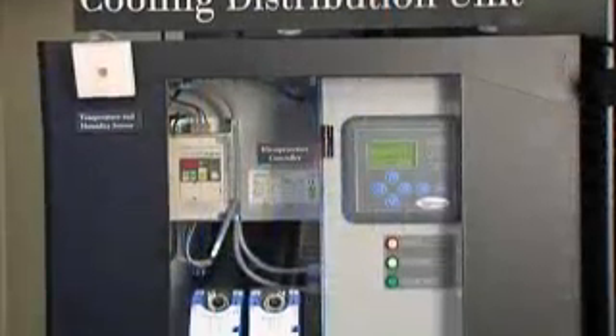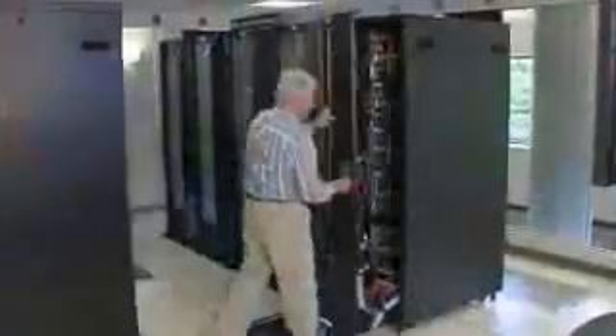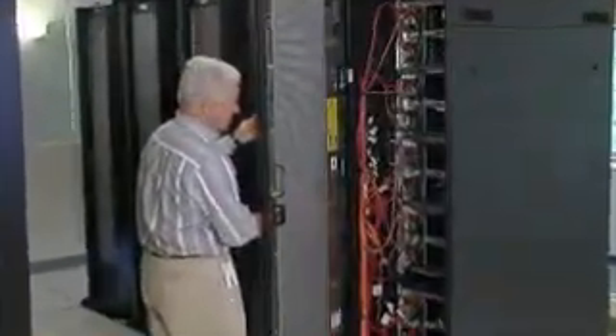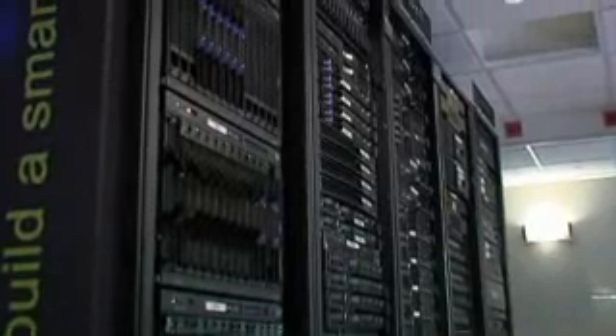After identifying the issues in the room and running through the modeling, we realized we needed to break the room up into two specific zones, an air-cooled zone and a water-cooled zone. The water-cooled zone is using cooling distribution units as well as rear door heat exchangers to take the heat away from the racks. In the air-cooled zone, we've identified exactly where the perforated tiles need to be to get the cold air directly to the machines that need it, as well as the creation of a true hot and cold aisle. While laying out the racks, we determined that we needed to load them from the bottom to the top, eliminating any air gaps either within the rack or in between racks to make sure that the air itself is not being contaminated or mixed between both the front and the back areas within the racks.